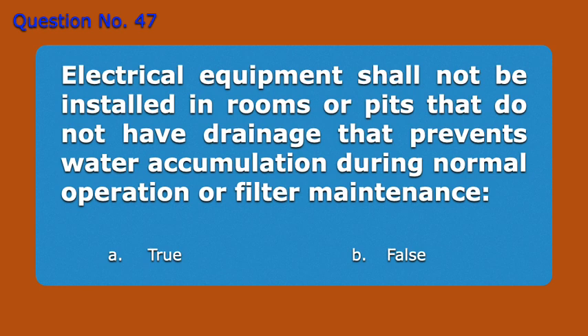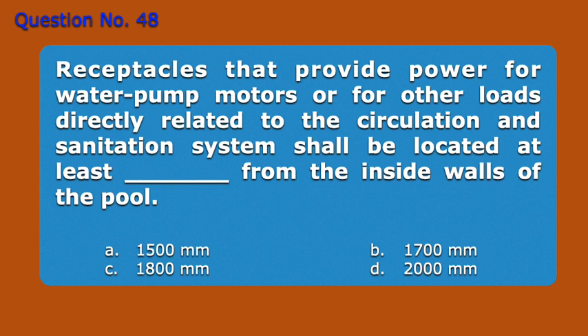Question number 47. Electrical equipment shall not be installed in rooms or pits that do not have drainage that prevents water accumulation during normal operation or filter maintenance. A. True, B. False. Answer A. True. Question number 48. Receptacles that provide power for water pump motors or for other loads directly related to the circulation and sanitation system shall be located at least blank from the inside walls of the pool. A. 1,500 millimeters, B. 1,700 millimeters, C. 1,800 millimeters, D. 2,000 millimeters. Answer C. 1,800 millimeters.